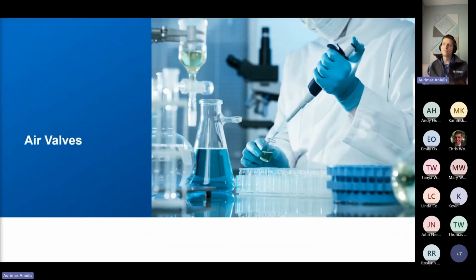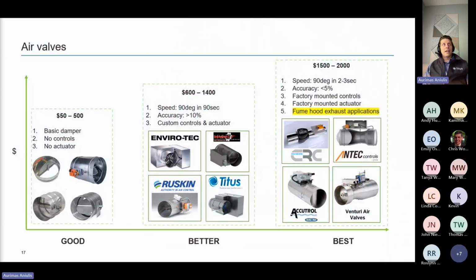And let's talk about air valves. I get asked a lot, why can't I just use VAV dampers in critical environment spaces? This example is geared to help people understand why not. So good, better, best, right? In the best column is where your Venturis live, along with some of the other valves on the market that are geared for these critical environments. The big difference is, first of all, the speed of the actuator and the accuracy of the valve, and most critical environment air valves come with factory mounted controls and factory mounted actuators. You get a packaged solution.